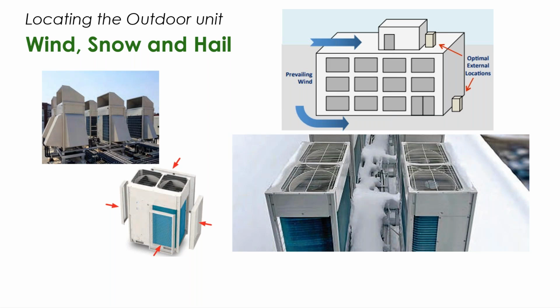Most manufacturers have some sort of snow blow setting that you can set on variable refrigerant systems. So if it is in a thermal off cycle, it will cycle that condenser fan on periodically to try to blow snow off of it, so that you can prevent any excess ice buildup leaking down into the fan blades, causing damage to the condenser blades or motors.